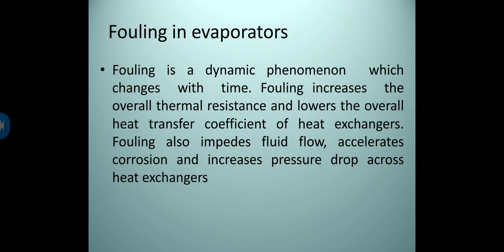Next one is fouling in evaporators. So see here, what is fouling in an evaporator? It is a dynamic phenomenon which changes with time. Fouling increases the overall thermal resistance and lowers the overall heat transfer coefficient of heat exchangers. Fouling also impedes fluid flow, accelerates corrosion and increases pressure drop across the heat exchanger, right?